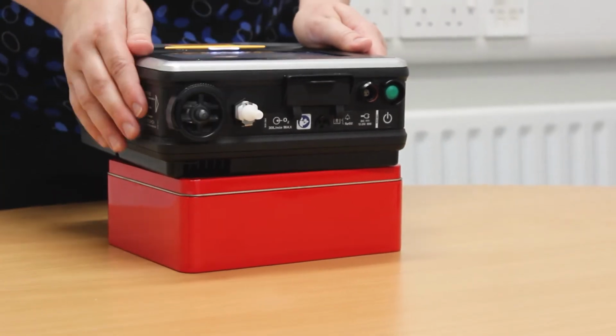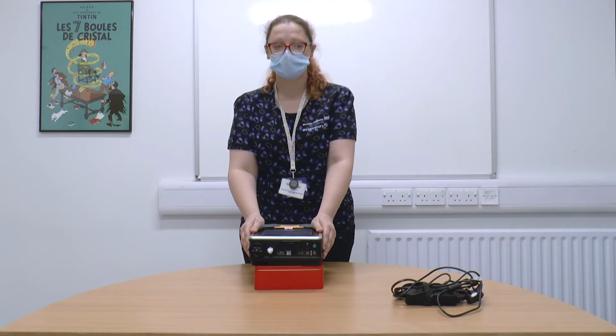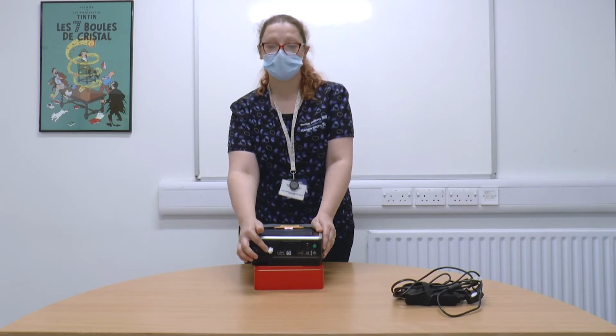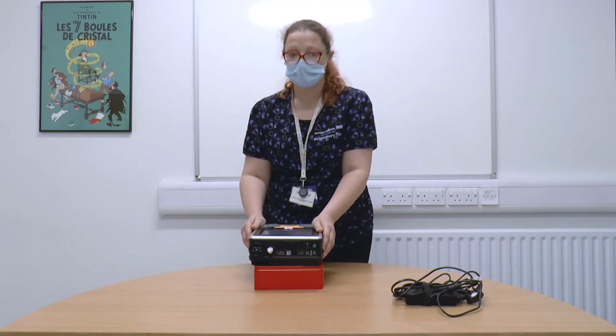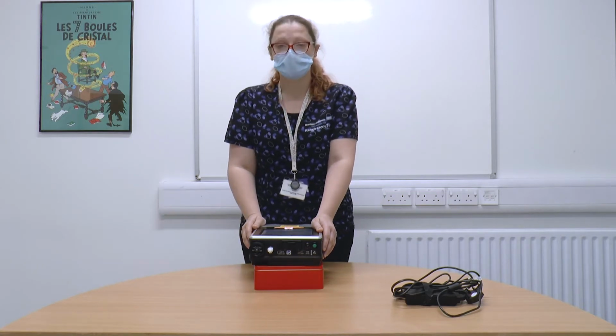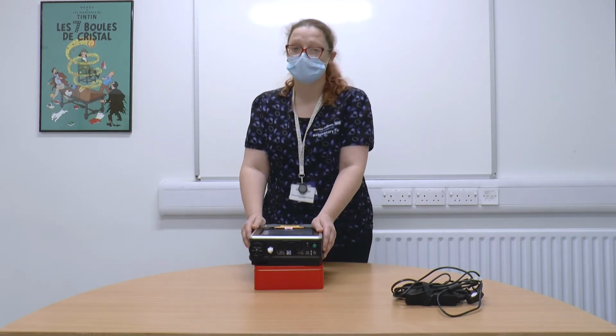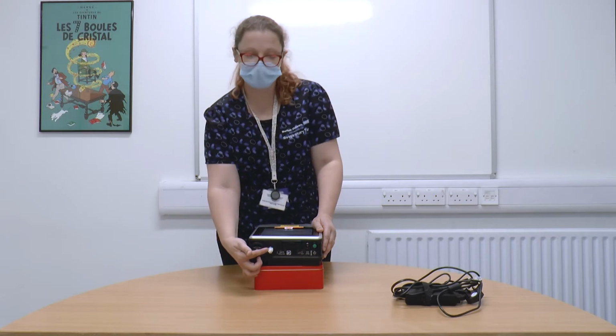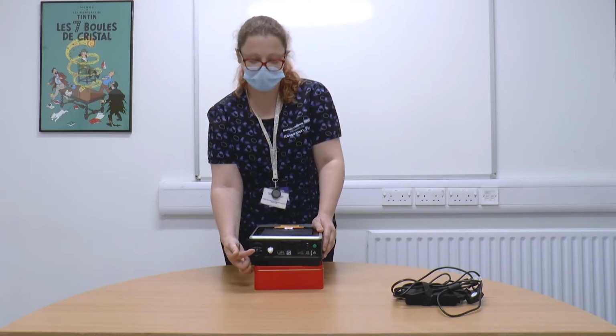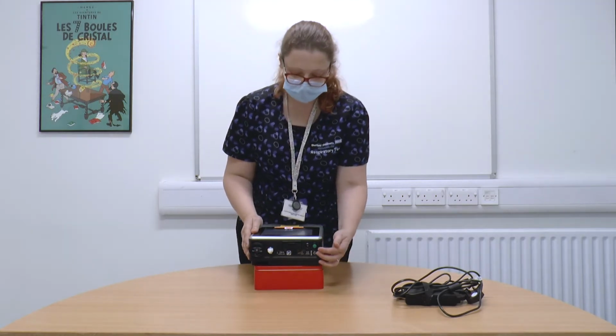If a child does not have an oxygen port attached to their ventilator, any Trilogy or Astral oxygen port will fit. Alternatively, you will have to use a front of circuit oxygen port, which you can only put 5 litres through. Because this is coming in where the air is coming in, you can use 15 litres.